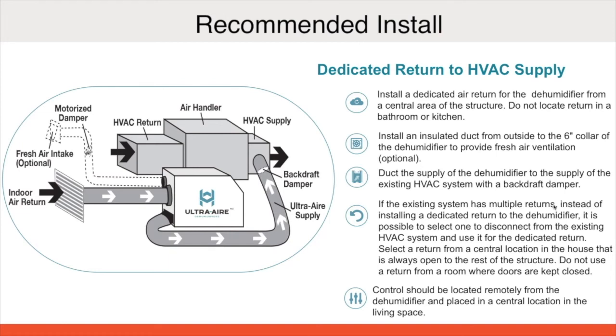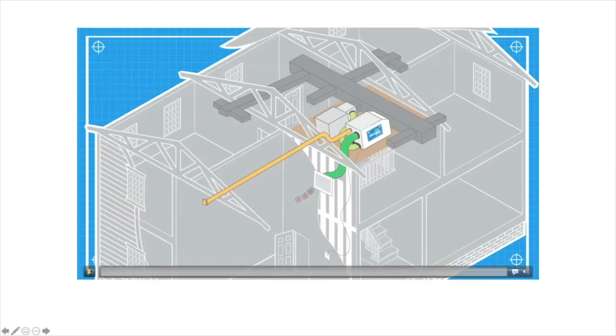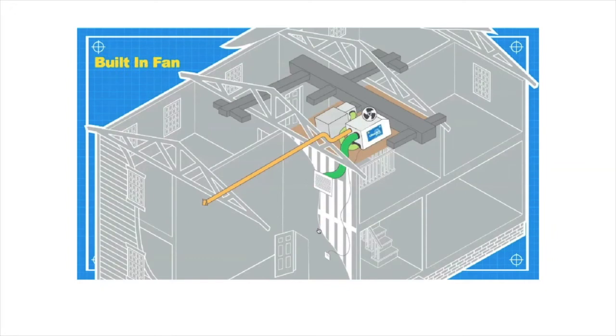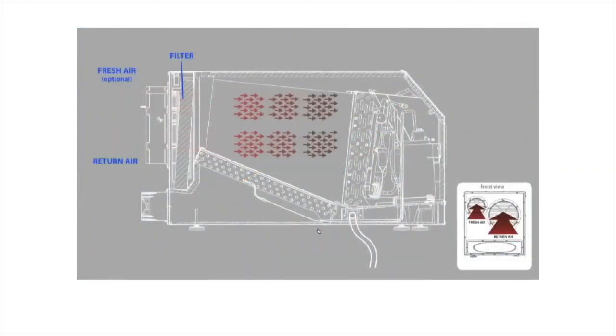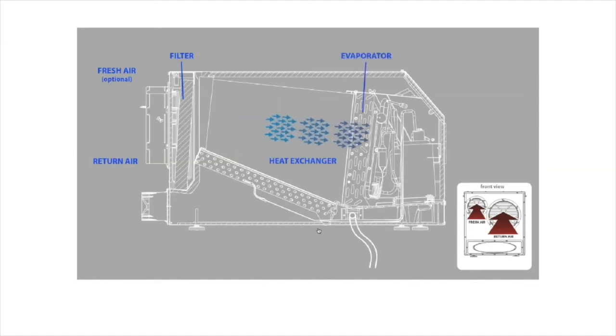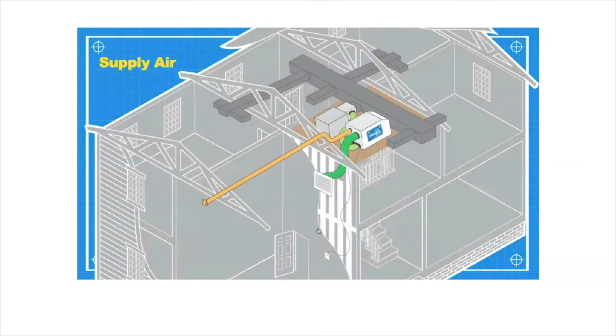Now, you don't have to use us for fresh air ventilation. You can use us just for dehumidification, but we always give you that option to use this for dehumidification or for ventilation as well. So this is how it looks as an illustration here. We're going to pull in air from that dedicated return into the dehumidifier with the fan. And then, if we want to, we can utilize the dehumidifier to bring in that outdoor air. And this is showing one of our XT units with that heat exchanger inside. We mix the air inside the dehumidifier. We're going to run it through the evaporator coil, have water go down the drain. And then we're going to deliver it back into the living space, and we're just utilizing the ductwork to distribute that dry air.